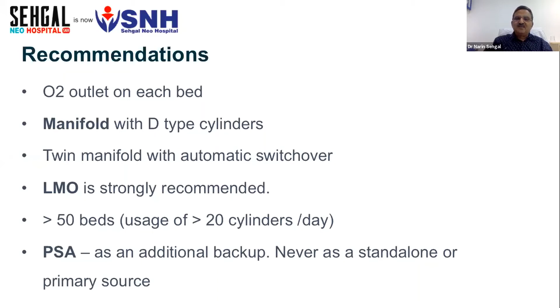If you are more than 50 beds, I think an LMO is strongly recommended, because typically a 50-bed hospital would be using 15 to 20 cylinders per day in normal circumstances, and one LMO micro cylinder of 200 liters is equivalent to about 22 cylinders. So that takes you through 1.5 days of supply. If you have 2 cylinders, then it's good enough for about 3 days, which keeps you secure and tension free. PSA is an additional backup, whose advantages and disadvantages have already been discussed. But with the advisory, more and more people are putting it in, and there is no denying that it is an additional backup. It can never be a standalone primary source, but it is an additional backup.